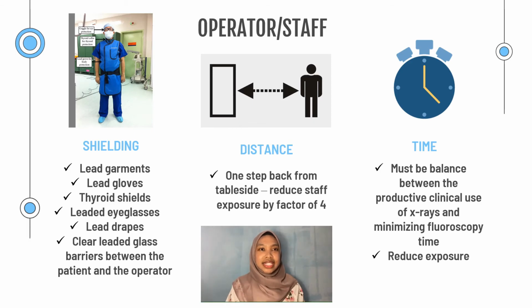Now I will present the second part in the safety of fluoroscopy, which is the safety for staff. The most important thing when handling fluoroscopy is the shielding. Shielding can be one of the protections against the radiation scattered around us. The shielding includes lead garments, lead gloves, thyroid shields, leaded eyeglasses, lead drapes, and also clear leaded glass barriers between the patient and the operator.